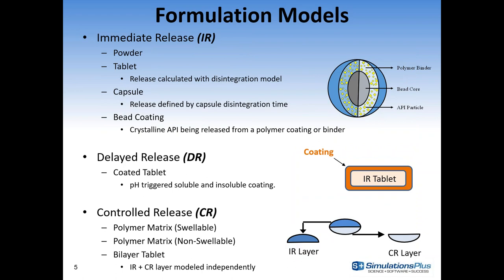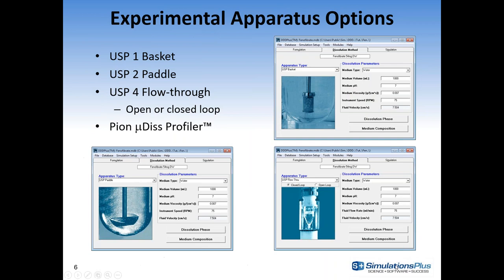The formulation models available in version 5 included powder, tablet, capsule, IR bead coating, a delayed-release coated tablet, CR controlled-release matrix tablets, and a bilayer tablet. The experimental apparatuses include USP1, USP2, USP4 flow-through in open or closed loop, and the Pion µDiss Profiler™. We've now added a new ASD — artificial stomach duodenum — apparatus model to DDD Plus version 6.